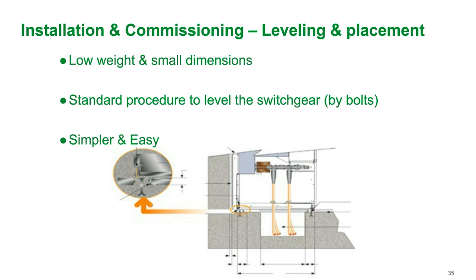With GIS, you do need to ensure that the switchgear is very level, because the bus bar connection, as in the old style of switchgear which requires sealing, requires a very tight tolerance of elevation change from section to section. So with a lot of gas-insulated switchgear, on this slide it's showing CBGS0, one of our Schneider GIS products. It has integrated leveling screws, so inside the frame you can adjust these leveling screws before you anchor the switchgear down, ensuring that you have the gear level across the whole lineup.